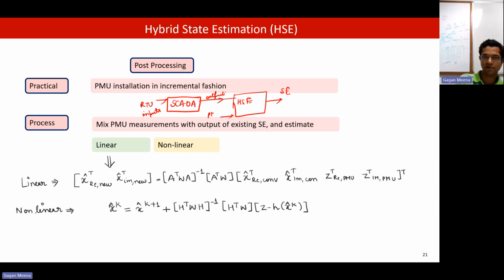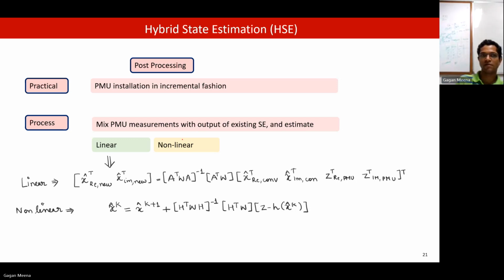Here we have PMU data also. Same thing is written here: output of PMU, earlier old plus new is equal to new. So this is practical now, where we are doing installation in an incremental fashion. Here the process is we mix the PMU measurement with the output of the existing state estimator and then do the estimation. Now this hybrid state estimator can be linear as well as non-linear.